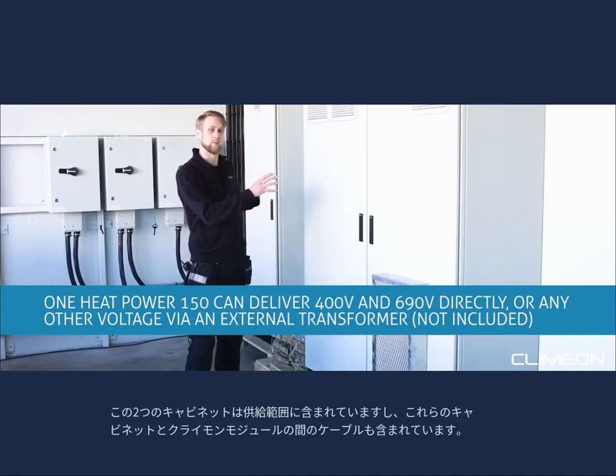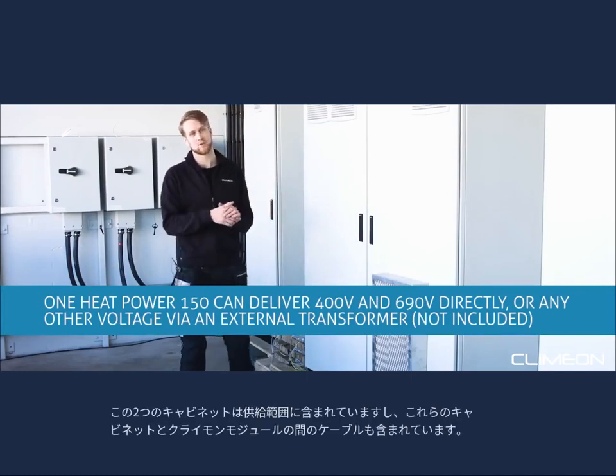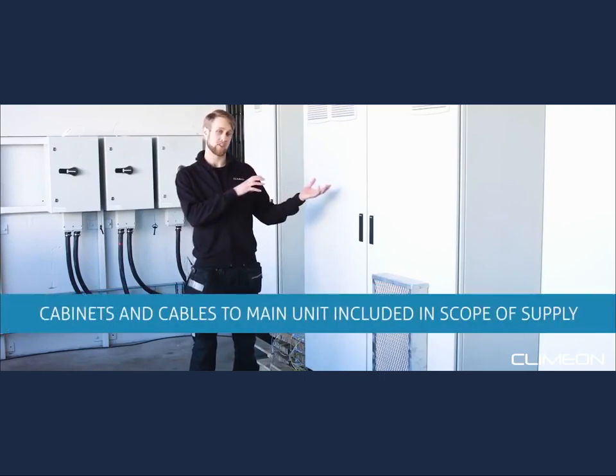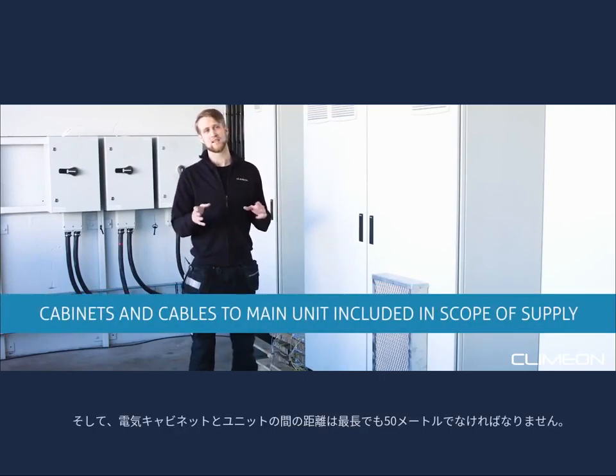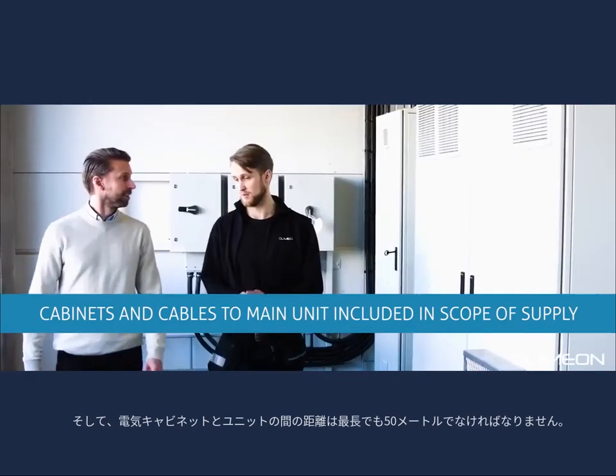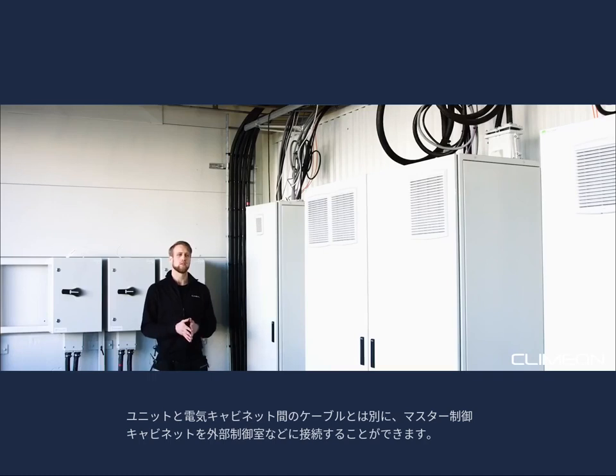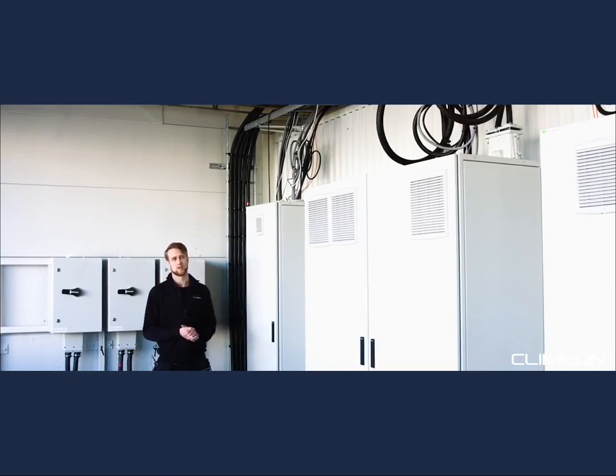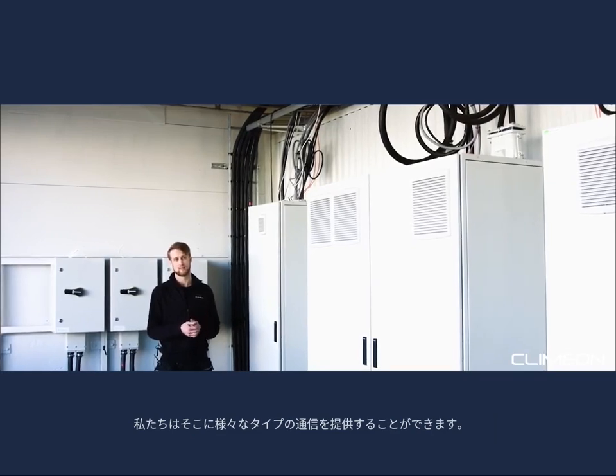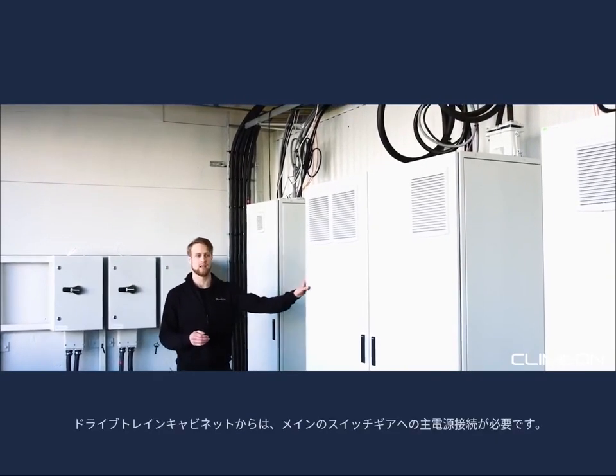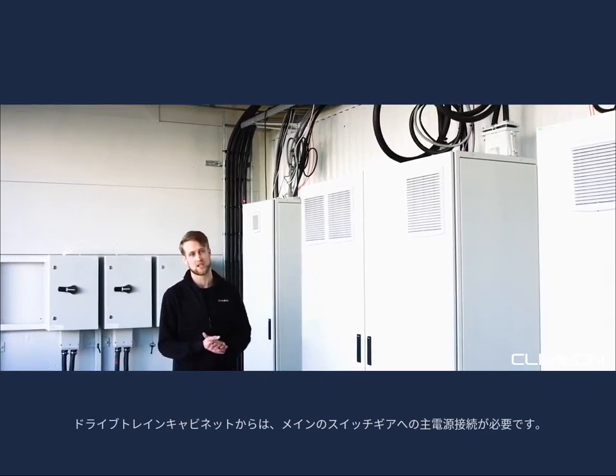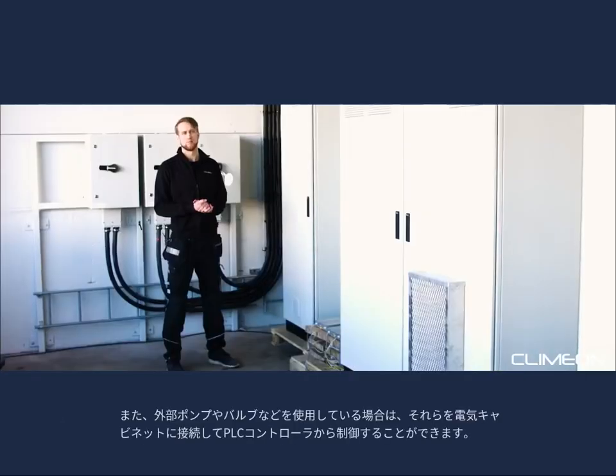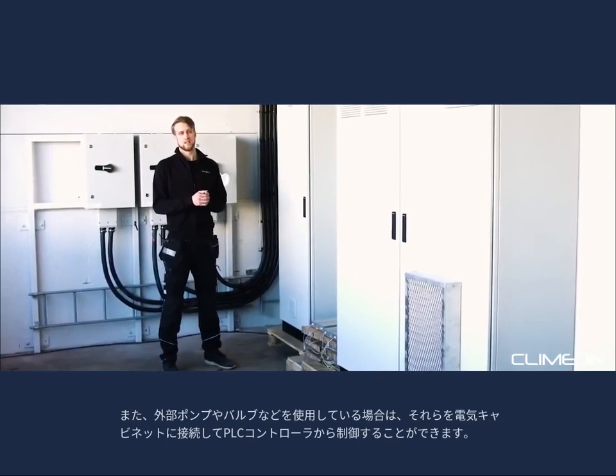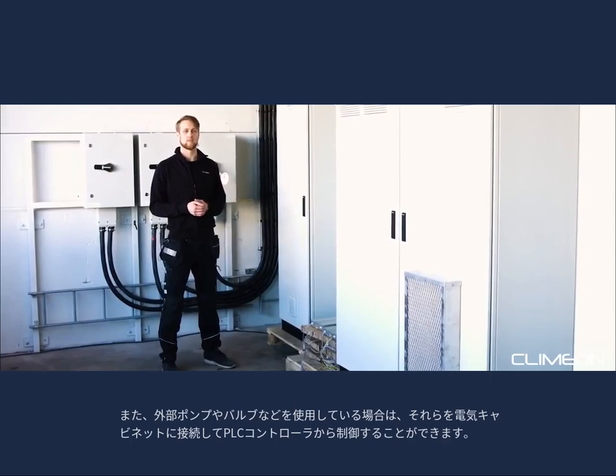So these two cabinets are included in the scope of supply, and also the cables between these cabinets and the Climeon machine. And the distance between the electrical cabinets and the unit should be maximum 50 meters. Apart from the cables between the unit and the electrical cabinets, you could connect the master control cabinet to an external control room or similar. There we can provide different communications buses, such as Modbus or Profibus or any other type of bus. From the drivetrain cabinet, you need a mains connection to a regular switchgear. In case you are using external pumps and valves, etc. for your integration, these can be connected to the electrical cabinets to control them from the PLC.